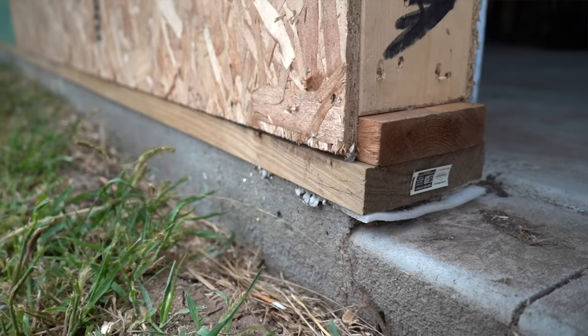The conditioned attic built into the SIPs roof system automatically puts all HVAC components in conditioned space. Mechanicals are typically half the BTUs needed — AC load can be cut in half, and you want it to be cut in half so the equipment runs at 100% efficiency. You want the system to run for a long time for dehumidification. Extreme Panel works with energy raters to help with sizing for wherever the house is. Matt notes how many southern attics are vented with ductwork in 140-degree heat — putting mechanicals under an R-52 lid changes everything.